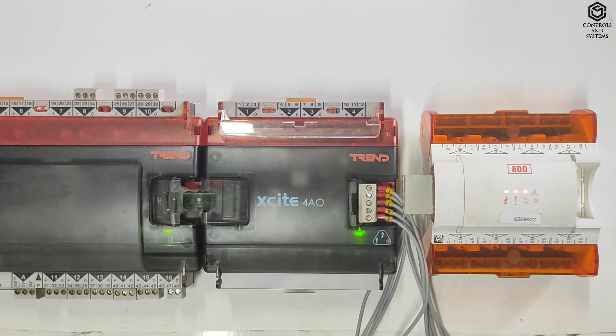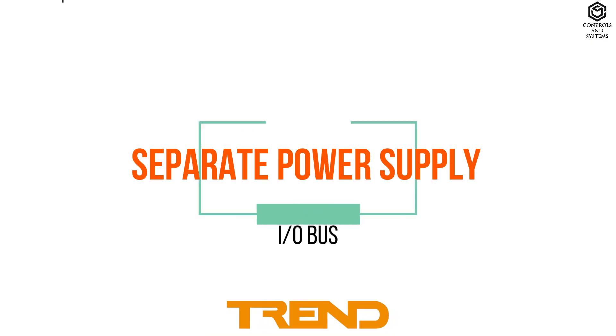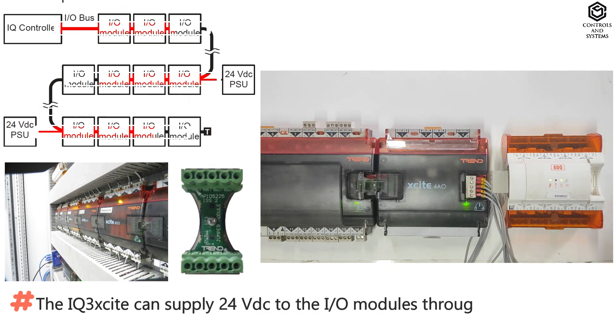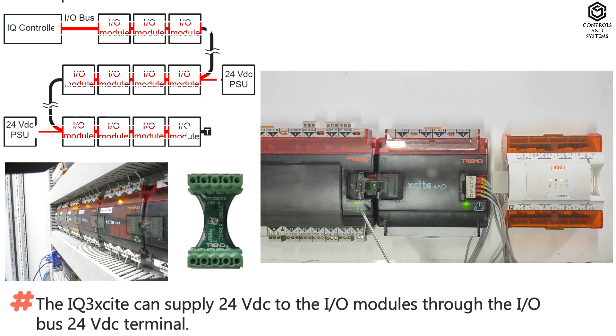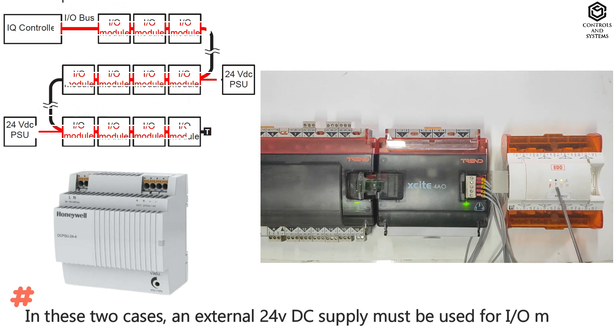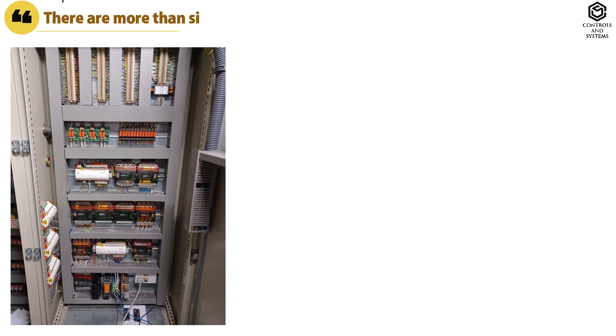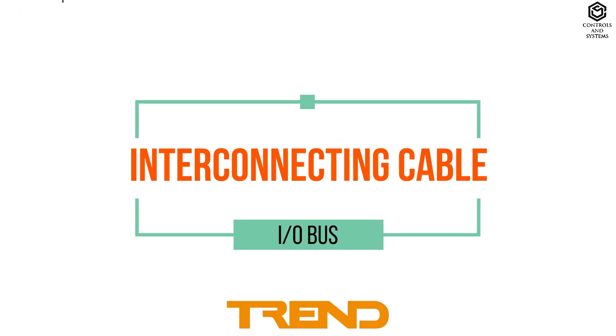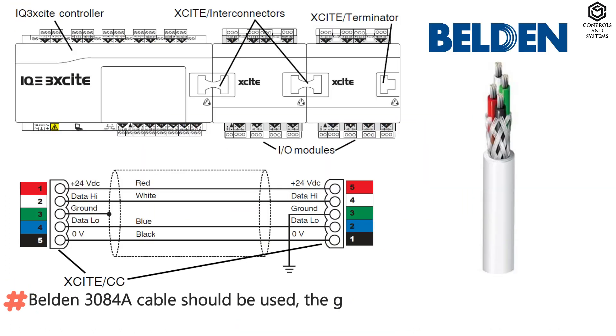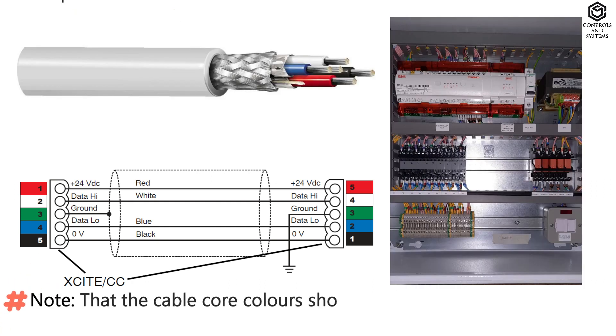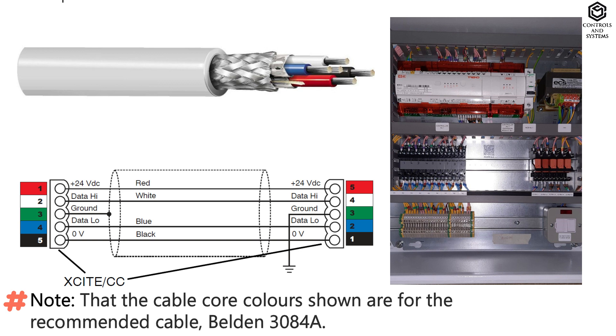Now switch on the IQ3 X-Site controller power supply. Separate power supply: the IQ3 X-Site can supply 24V DC to the I.O. modules through the I.O. bus 24V DC terminal. In these two cases an external 24V DC supply must be used for I.O. modules: first, when there are more than 6 I.O. modules; second, when the main controller combined supply would be overloaded. Interconnecting cable: Belden 3084A cable should be used. The ground connector should be earthed locally and the cable screen should be grounded at the controller end.